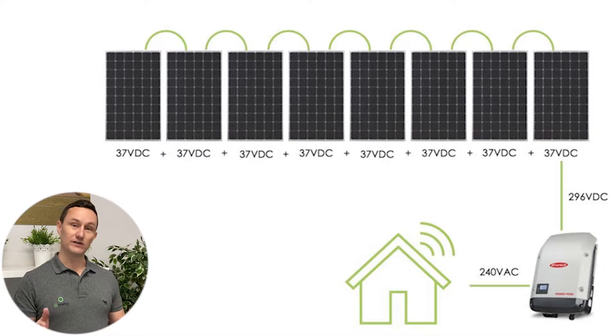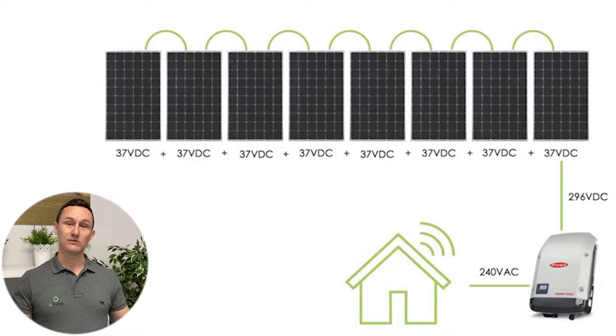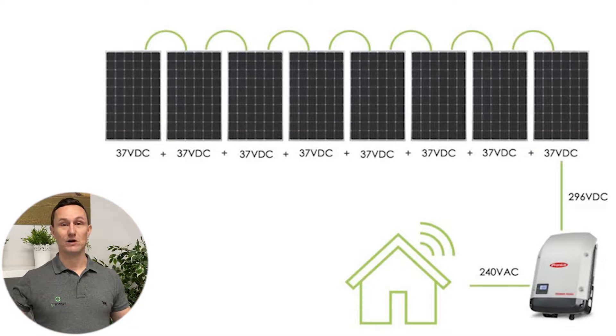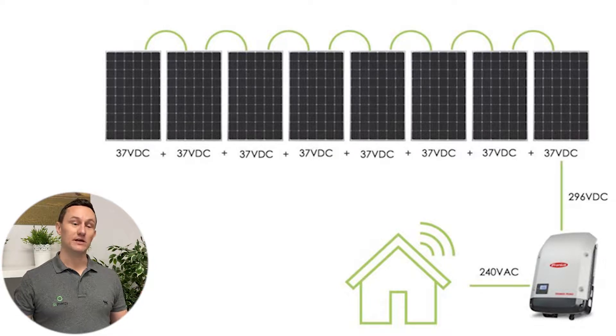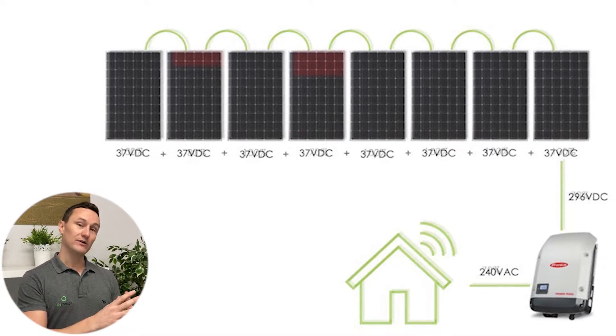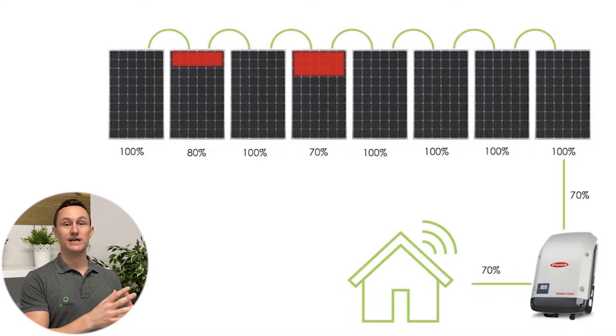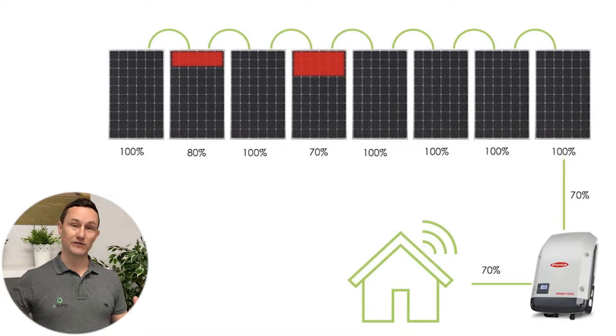There is an article on our website that explains this further, but basically a string inverter means that you've got a string of panels connected together — perhaps five or up to about 12 panels in a string configuration. What that means is, if one of those panels in that string is affected by shade or debris, the whole string of panels is going to be affected by that weakest link.